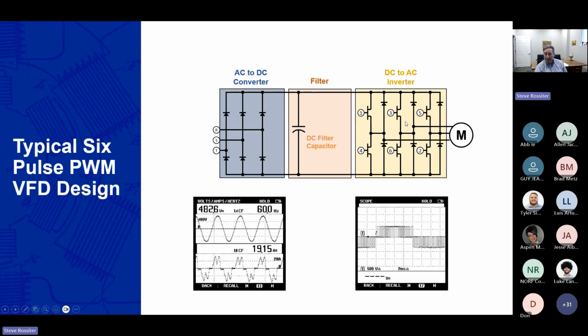Now on the back end, on the inverter end, and of course variable frequency drives start off as adjustable speed drives, adjustable frequency drives, inverters. Inverters comes from the fact that you're really taking the DC and inverting it back to AC and just using transistors. And that's done with a PWM waveform, which turns that voltage on and off in different widths, which synthesizes the waveform.